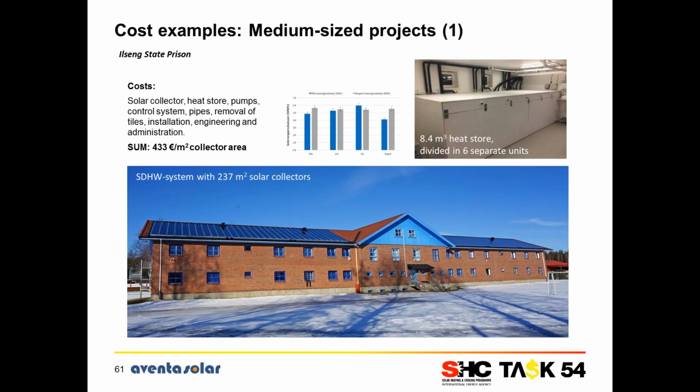The costs I'm giving here are related to collectors, heat store, pumps, control system, pipes, removal of existing tiles, as it was a retrofit project, and installation, engineering, and administration. And we end here with a cost of 433 euros per square meter, if you normalize it to the collector costs. Collector area, I apologize.